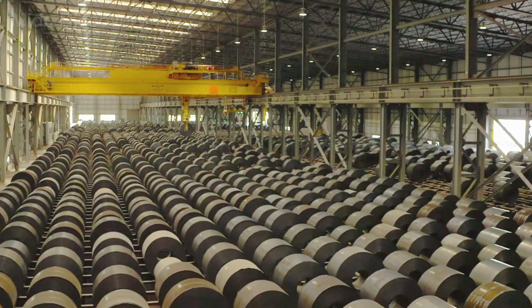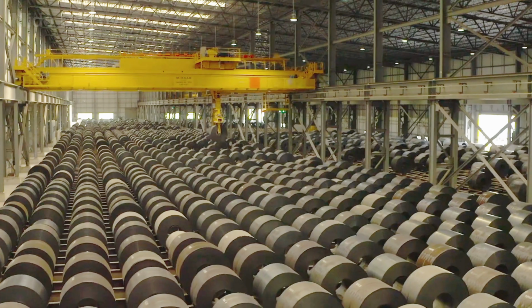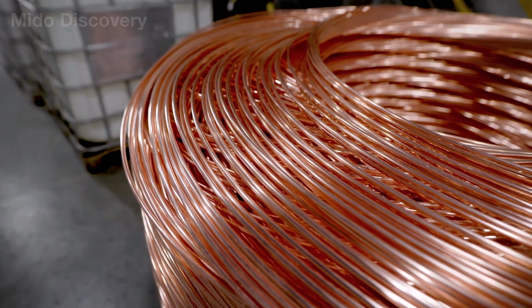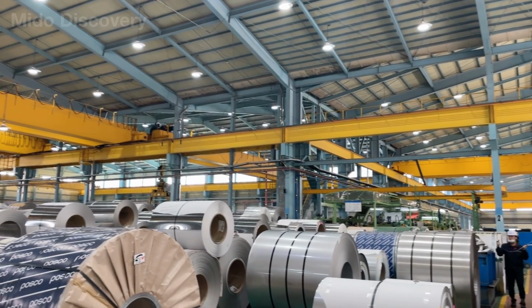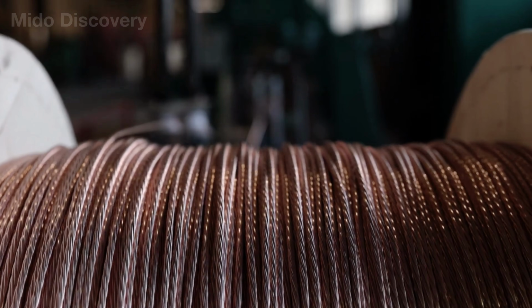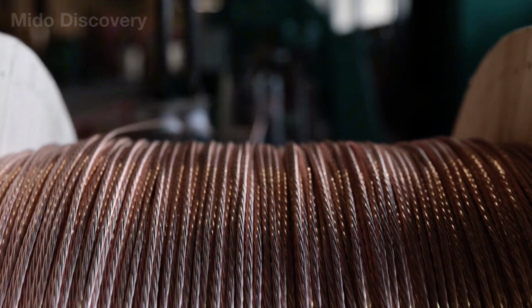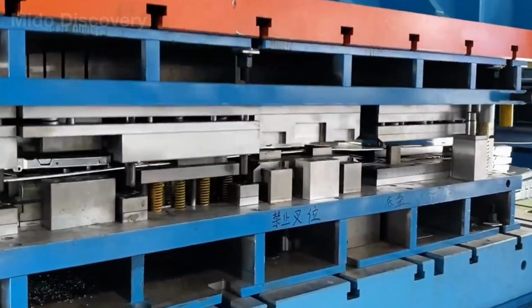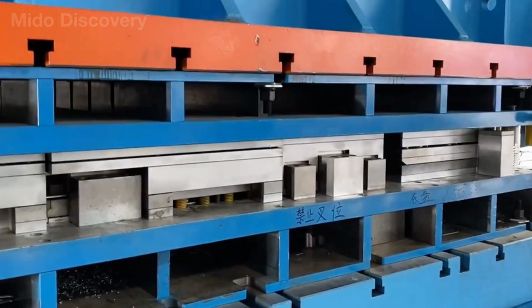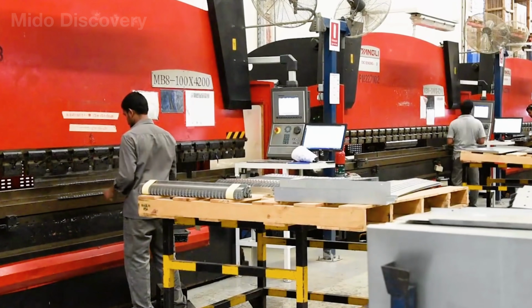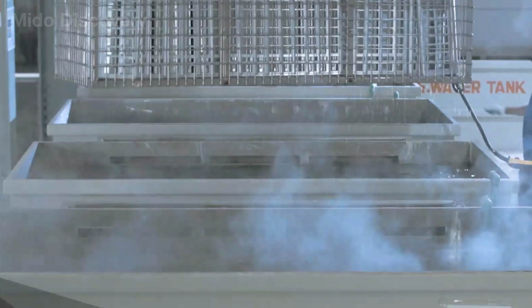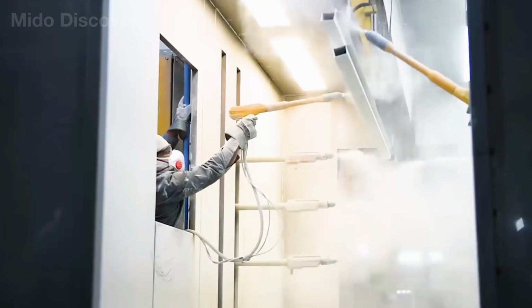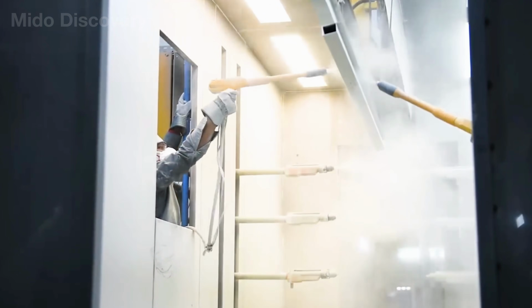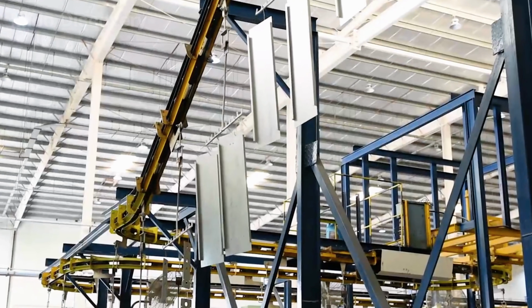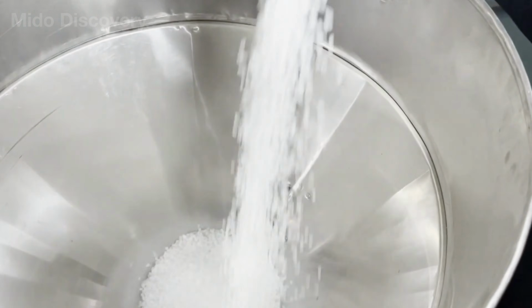From coils of steel, copper tubing, and thousands of individual components, an air conditioner gradually takes shape through a series of precisely controlled stages. The cabinet is formed, the heat exchangers are bent and assembled, while the compressor, fans, sensors, and control board are integrated into a closed-loop system. But the process is only complete when every brazed joint passes leak testing. The refrigerant circuit is evacuated, and the exact amount of refrigerant is charged. The indoor and outdoor units must then prove their cooling performance, safety, and quiet operation before being packaged.